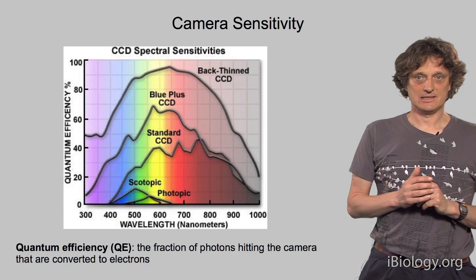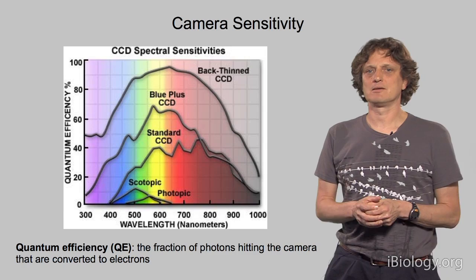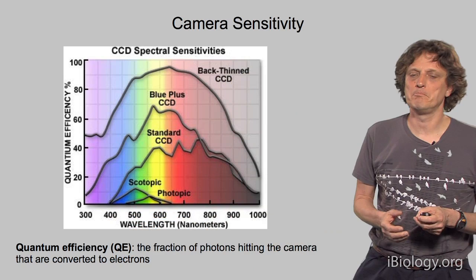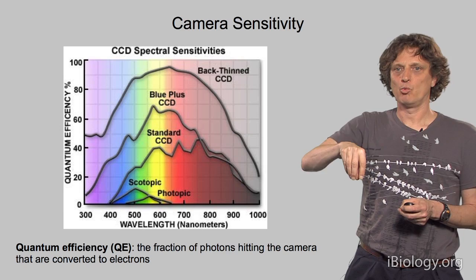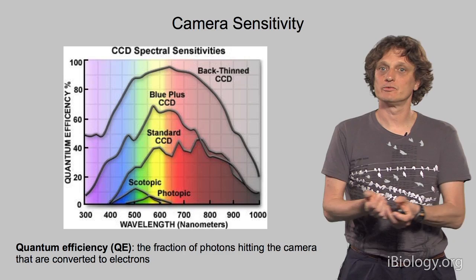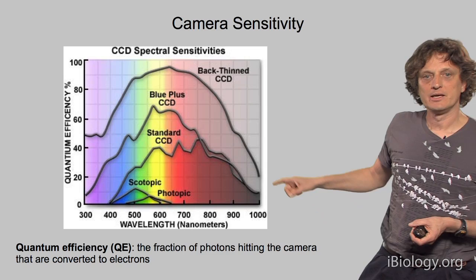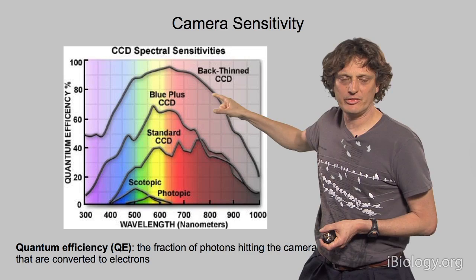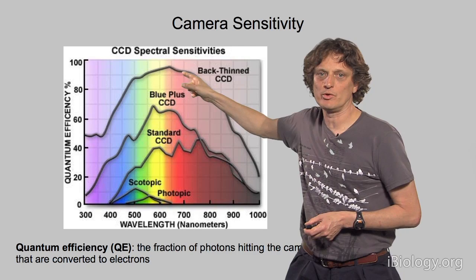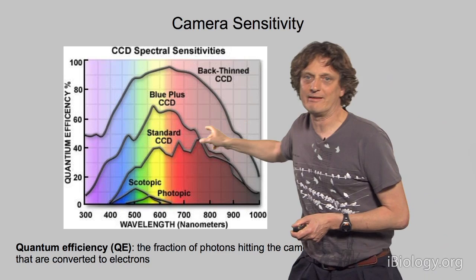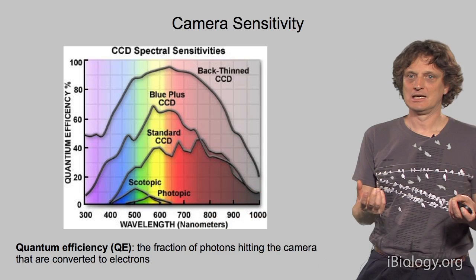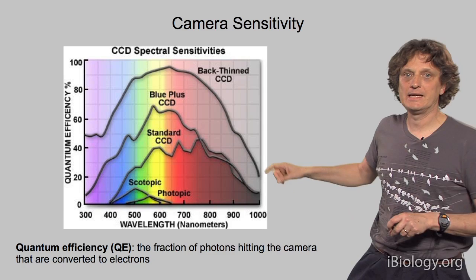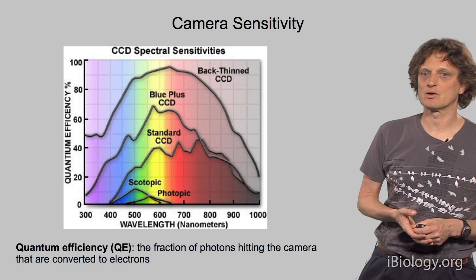Another very important camera parameter is sensitivity, and the most important measure is quantum efficiency — the fraction of photons hitting the camera that are actually converted into detectable electrons. Quantum efficiency depends on chip design; back-thinned CCDs can have very high quantum efficiency, up to 95%. It is also wavelength dependent, so you want to match it to your dyes. Many cameras nowadays have between 70 and 95% quantum efficiency.